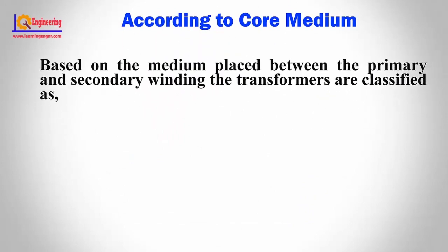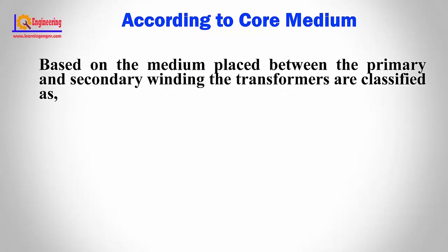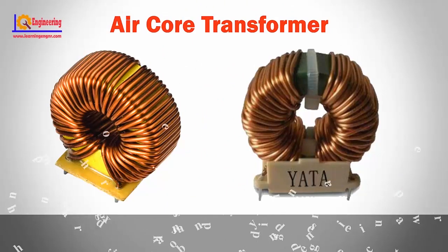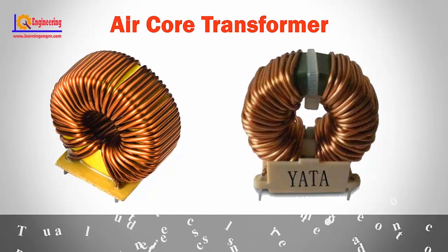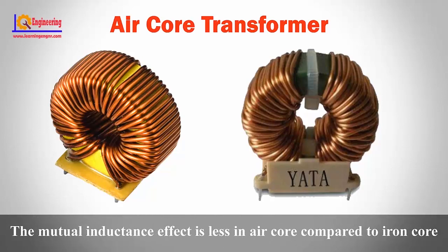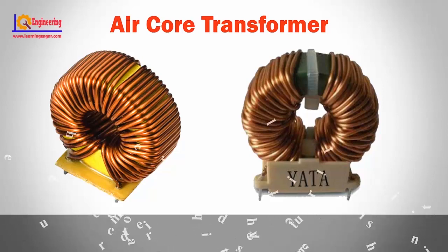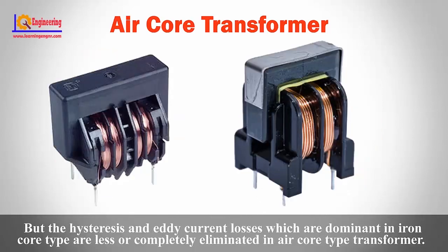According to core medium, based on the medium placed between the primary and secondary windings, transformers are classified as air core transformer and iron core transformer. In an air core transformer, the primary and secondary windings are wound on a non-magnetic former where the flux linkage between primary and secondary is through the air. The mutual inductance effect is less in air core compared to iron core, and the reluctance offered to the generated flux is high. However, hysteresis and eddy current losses, which are dominant in iron core types, are less or completely eliminated in air core transformers.